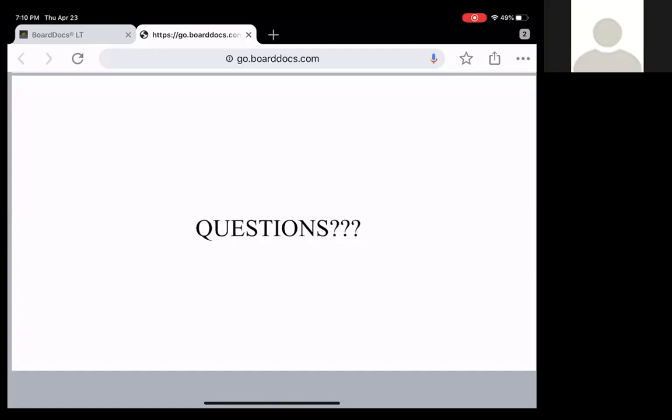So I could tell you one of the issues I had in our walkthrough is the rotunda there with the skylight and the way the ductwork came in, the air patterns. I had some issues with how that was designed. It's been that way since the building was built. Now we've put in dehumidification, which Tim shared with me the design. It's pretty straightforward. I have no issues with that, other than the fact that we have to do that.